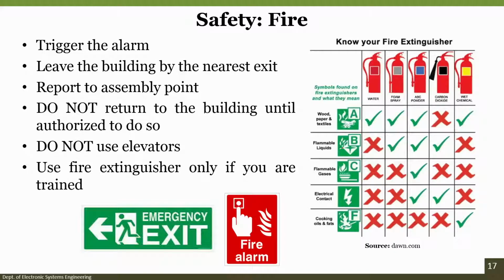If flammable liquids are burning, you can use foam spray, ABC powder and carbon dioxide. You cannot use wet chemical and water. Same thing for flammable gases, you can use only ABC powder. For electrical contact, ABC and carbon dioxide. Finally, for cooking oils and fats, if there is a fire, you should only use a wet chemical kind of fire extinguisher.